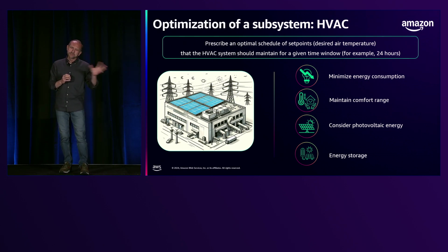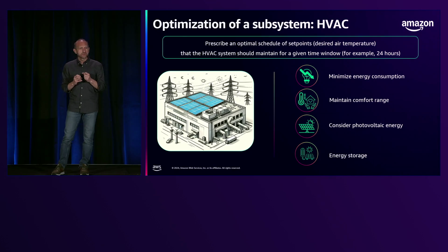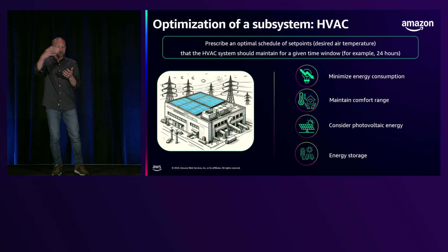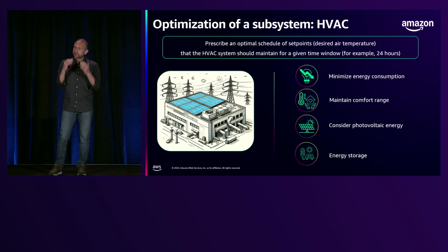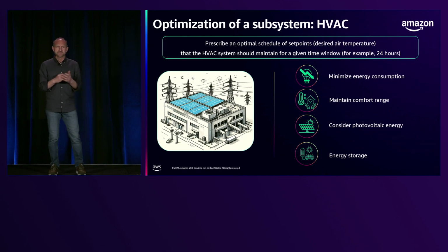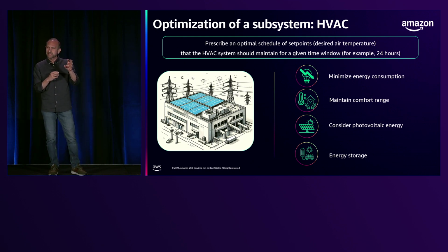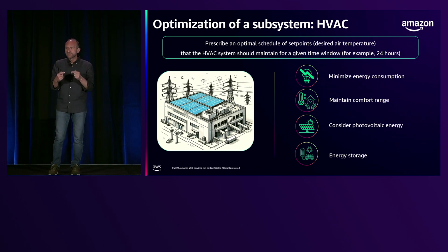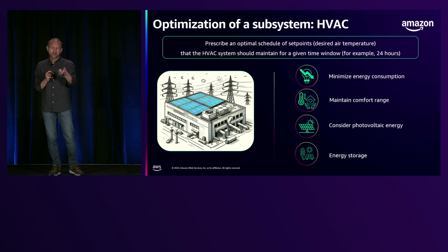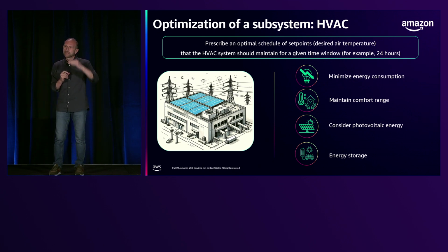But there's also another alternative. Exploiting, for example, variable photovoltaic production during the day, where we have a peak of production at midday because temperatures are high, we could pre-cool the site, lowering the set point to 70 degrees. Then, once photovoltaic energy production reduces later in the day, we can progressively let the site warm up, and intervene again, switching the set points once more, right before reaching the threshold of 80 degrees.